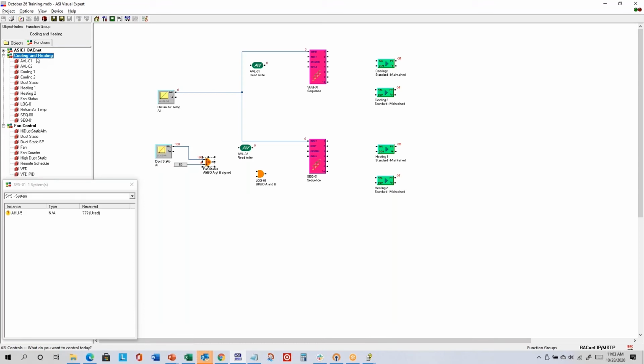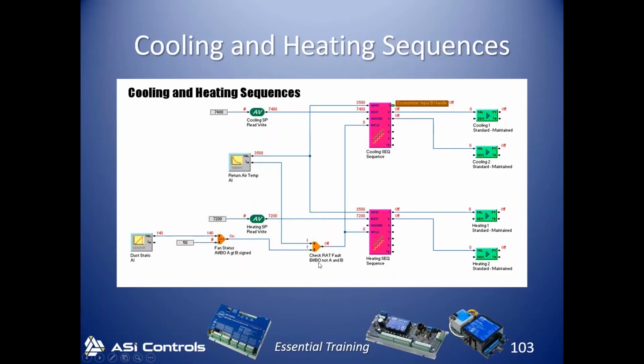And so I can go back to the graphical programming group. And then the second logic type is a binary input / binary output logic type. So I'm going to have two binary inputs and the binary output will turn on if the A value is off. Not A means if A is off, and the B value is on. So I want it to turn on if my return air temp is not in fault, meaning no wiring errors, and fan status is on.